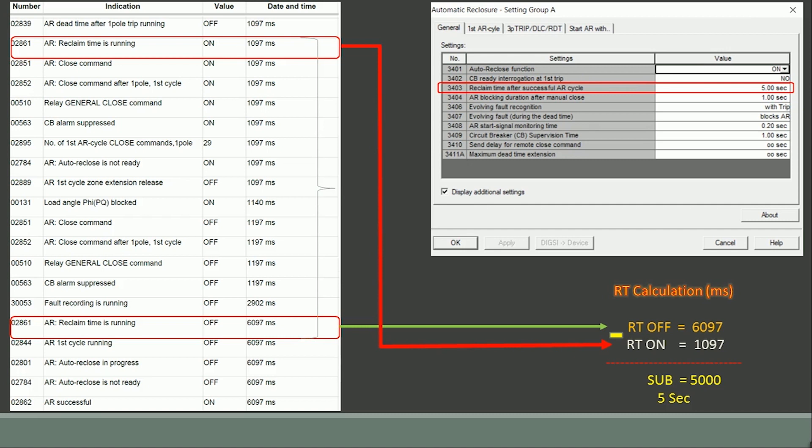Within this reclaim time no more fault occurred and the relay is going to successful auto reclose verified in parameter number 02862.